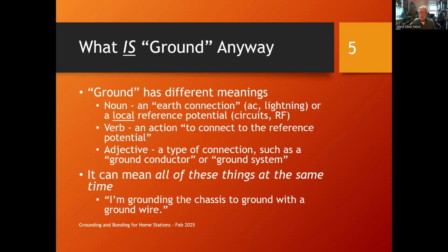When you use this word, it's overused, and you have to make sure the other person understands how you're using it. So the British, for example, have recognized this for many years. And when they talk about connecting something to the earth, they call it earthing as opposed to grounding. And so they differentiate between an actual connection to the earth and these reference potentials, and that helps some of the confusion.